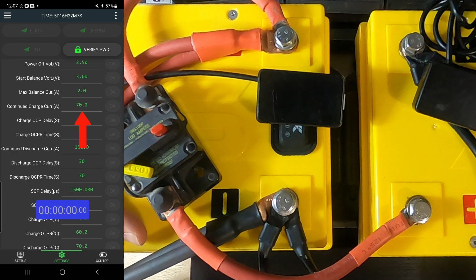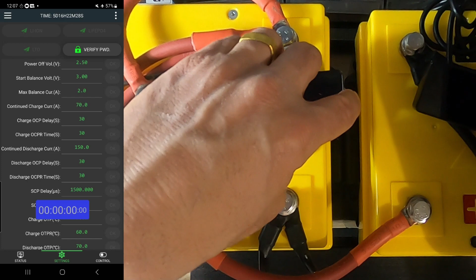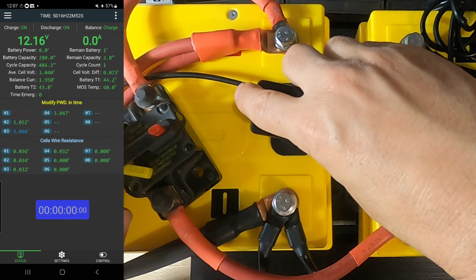On our discharge curve, we get that sharp decline from 3.65 down to about 3.40, and we settle in around 3.2 all the way down to like 10%. Then we get a sharp drop off below 3.2, and that's where the amps, the transference, should start increasing exponentially when we connect these batteries in parallel.